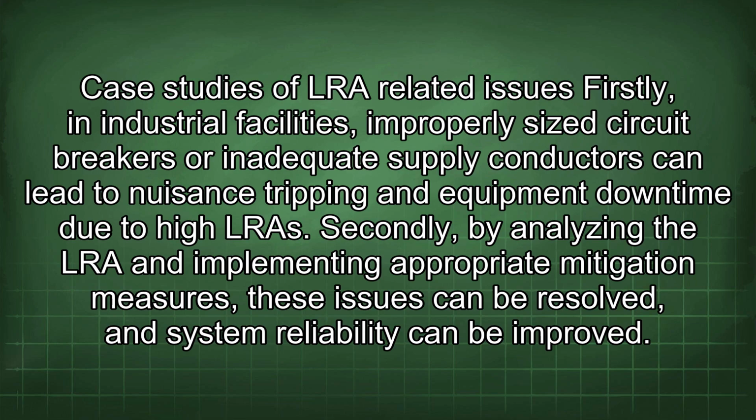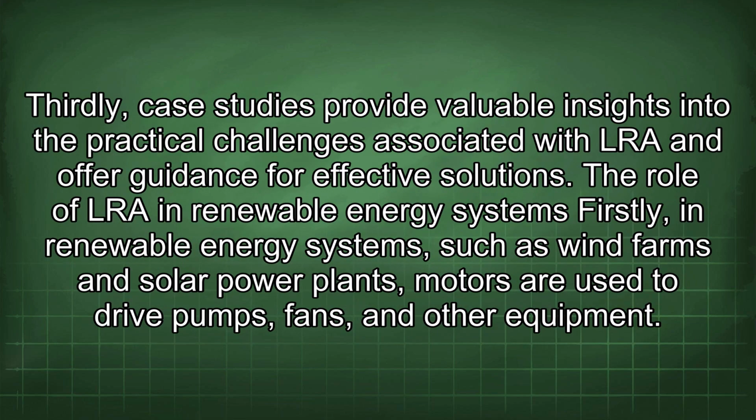Case studies of LRA-related issues. Firstly, in industrial facilities, improperly sized circuit breakers or inadequate supply conductors can lead to nuisance tripping and equipment downtime due to high LRA. Secondly, by analyzing the LRA and implementing appropriate mitigation measures, these issues can be resolved, and system reliability can be improved. Thirdly, case studies provide valuable insights into the practical challenges associated with LRA and offer guidance for effective solutions.